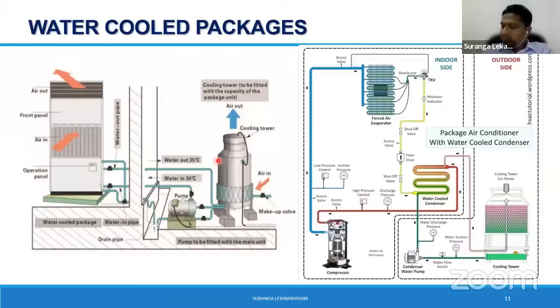Then you can find water cooled packages in the industry. If you go to food cities or small scale shopping malls, most of them rely on water cooled packages. There you can see the package unit here, which has both your evaporator and the condenser. The condenser is cooled by your cooling tower water. So you need to have your cooling tower and the condenser water pump to circulate the condenser water through the circuit. Right, so that's mainly about the water cooled system.